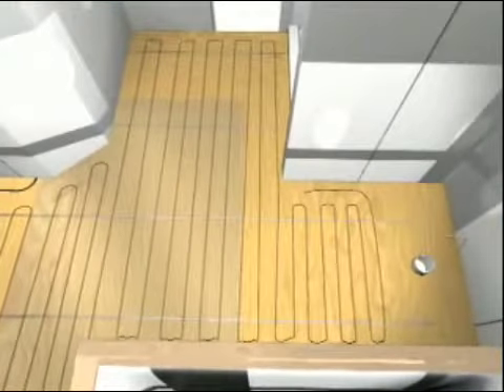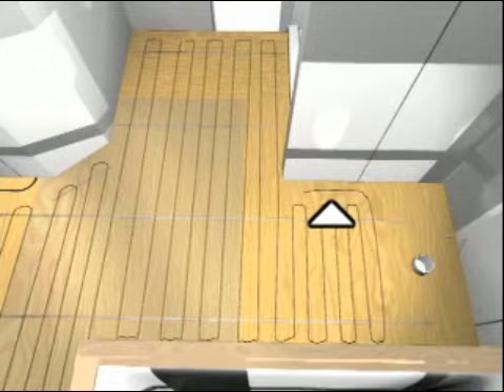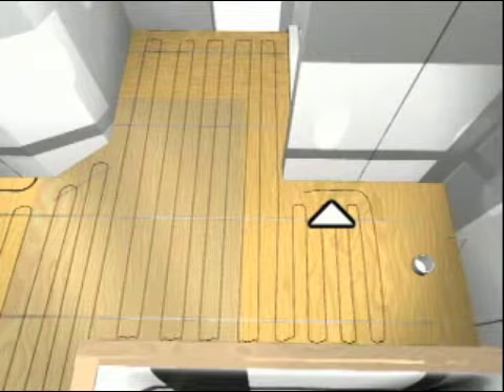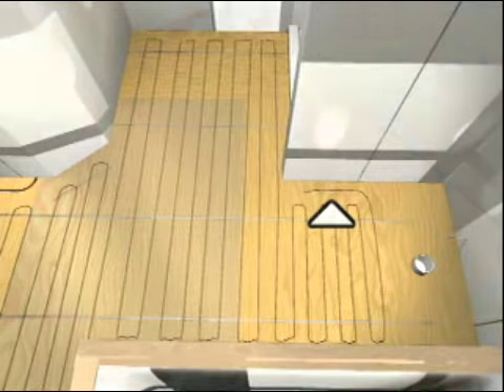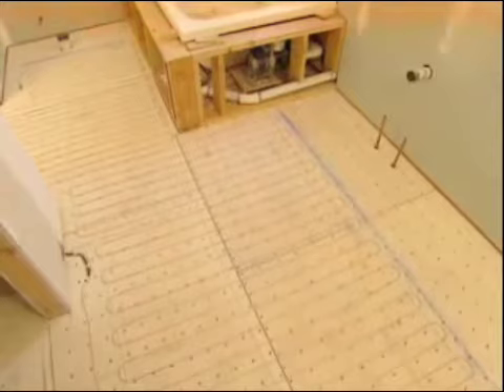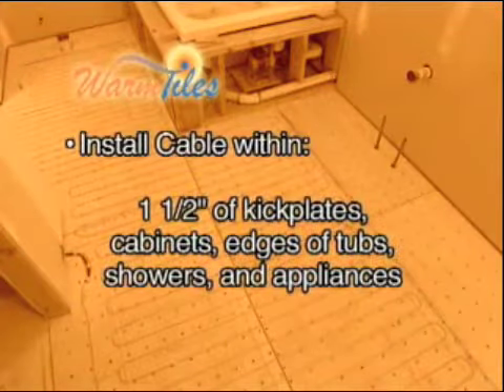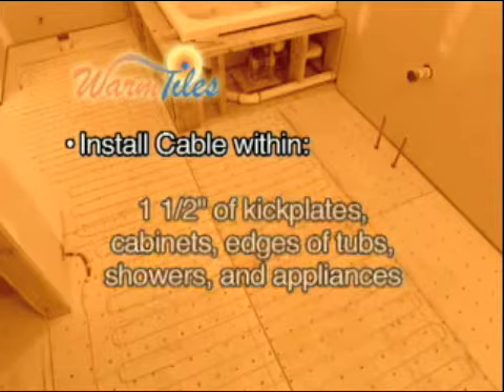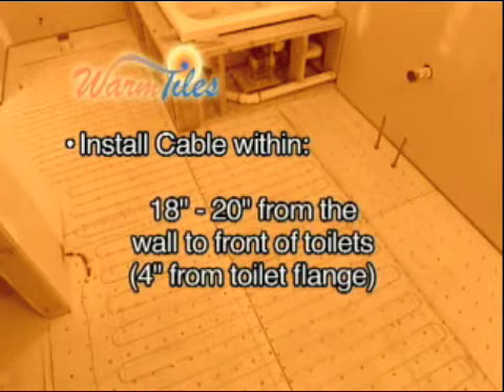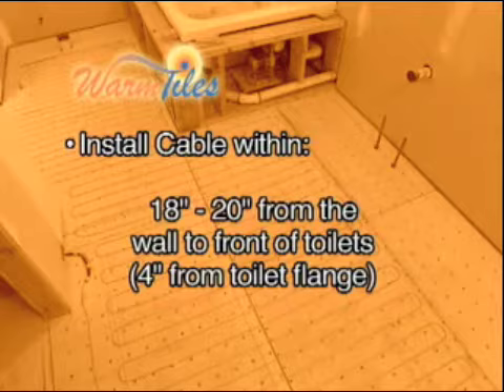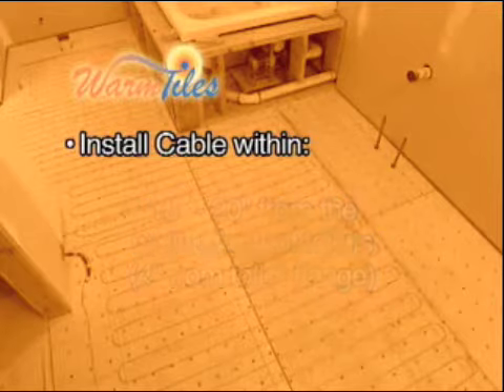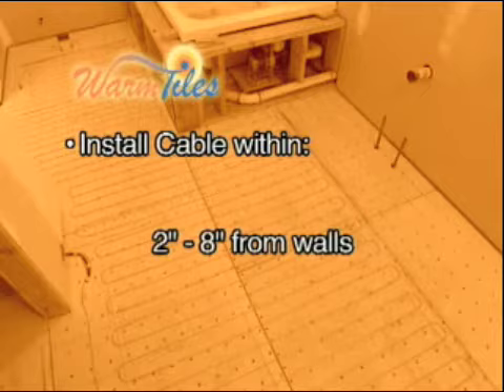Plan for the cable layout to end in a low traffic area or allow a 3-inch channel at the edge of the cable installation back to the low traffic area to route any excess heating cable there. The cable should be installed within 1.5 inches of kick plates on cabinets, edges of tubs, showers, and appliances, 18 to 20 inches from the wall to front of toilets, making sure to be 4 inches from toilet flange, and 2 to 8 inches from walls as referenced in the warm tiles installation instructions included in your kit.